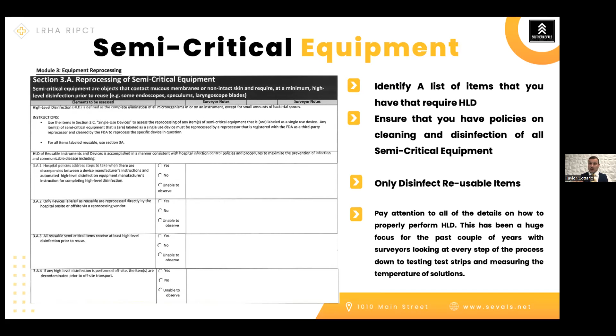Also, we're going to go through this, but pay attention to the details. Again, I'm going to reemphasize this throughout this whole presentation, is that for the past couple of years, surveyors, not only state, but your federal surveyors, have dove deep into the process for all those different things, even down to testing of the test strips. So make sure that you're looking at all those things, and we're going to touch on those key items as we go through this. More about semi-critical items, you want to make sure that with your endoscopes that you're processing, or different pieces of equipment, that you perform inspection of the items before, during, and after the leak test. So, before you use the item, make sure, is that endoscope dripping?